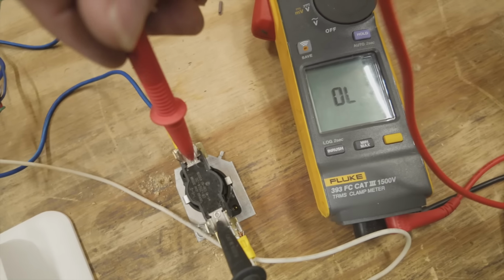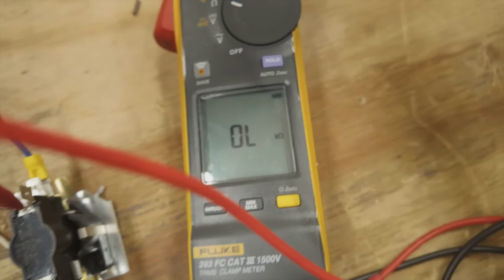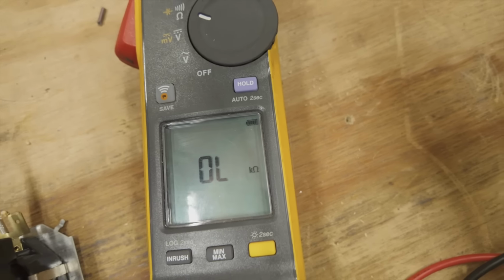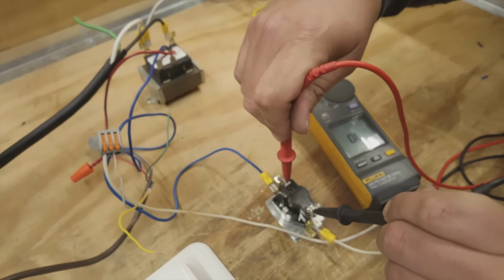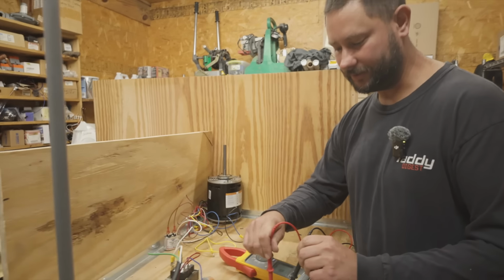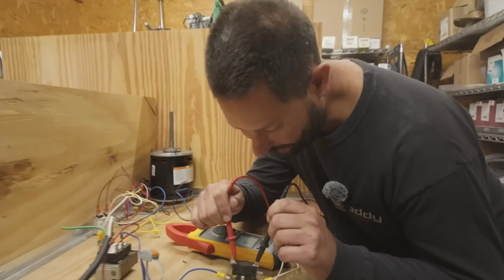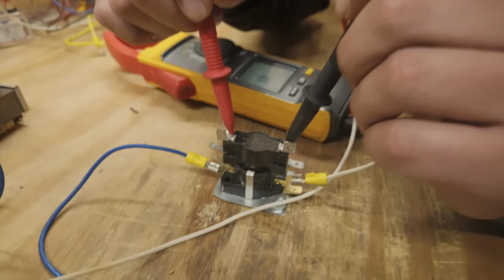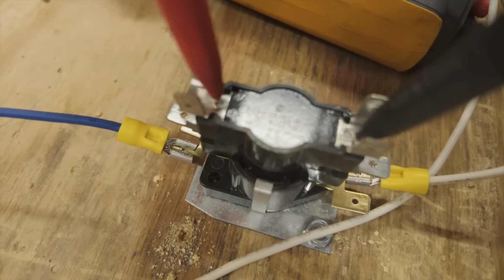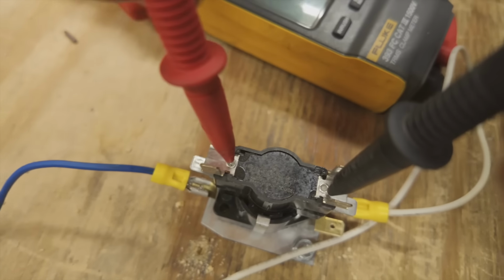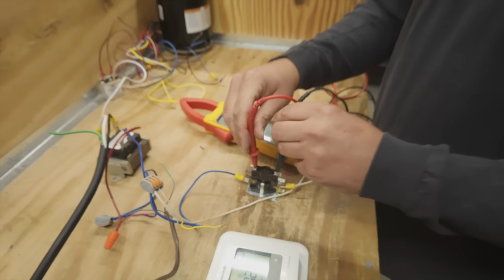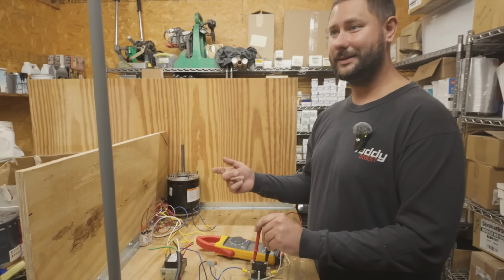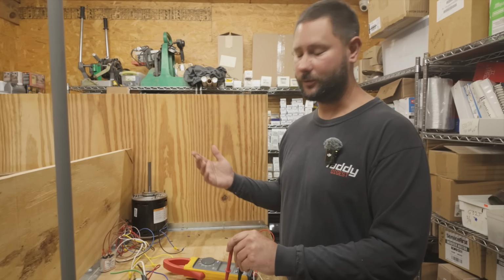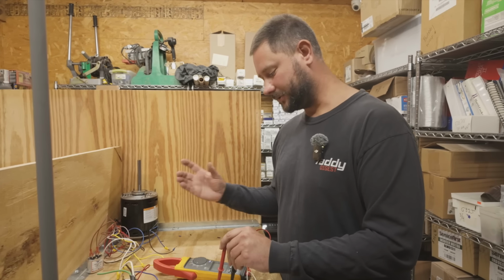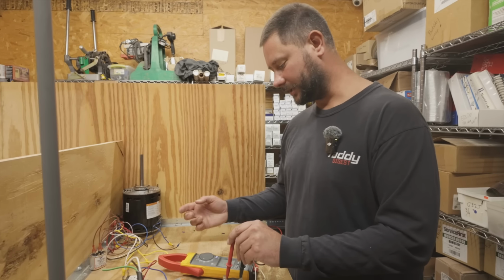Check contacts. Contacts are still open. Well, could it be bad? No, it's not, because it's got a delay. You see? And you can actually see what the delay is on it usually. This one says C3060 H145. So if you know how to read that, you'll know whether it's 30 seconds, 60 seconds, 90 seconds, 45 seconds. Each sequencer is different. It's going to close in just a minute.